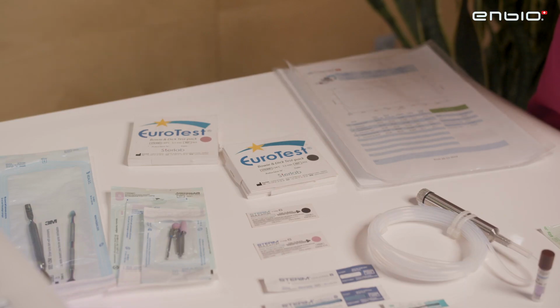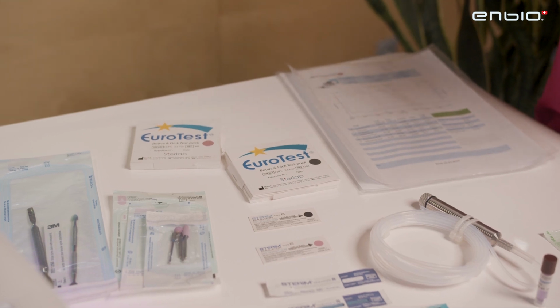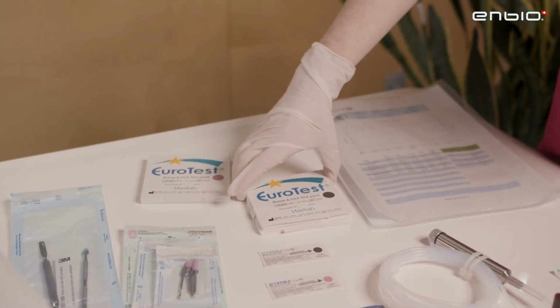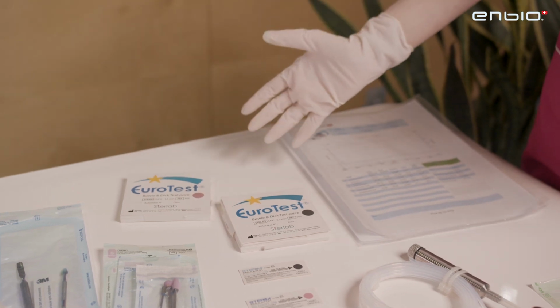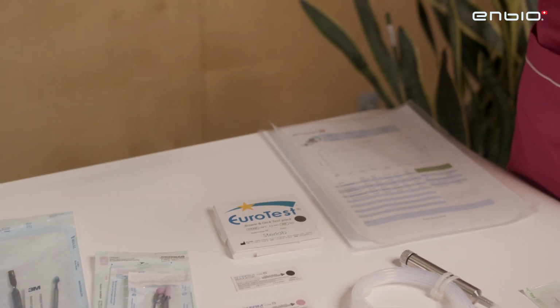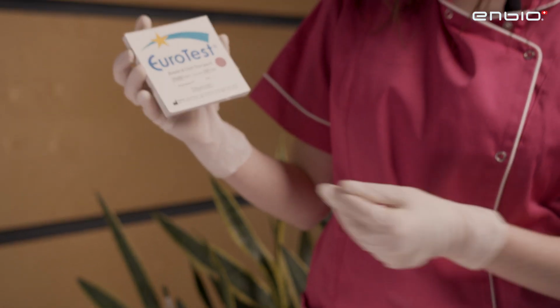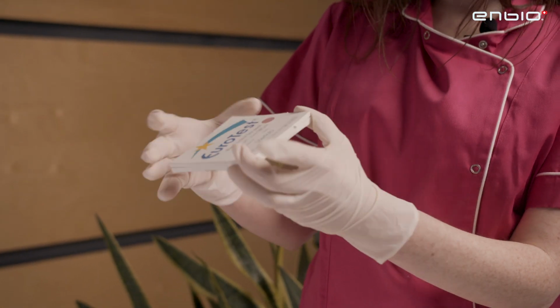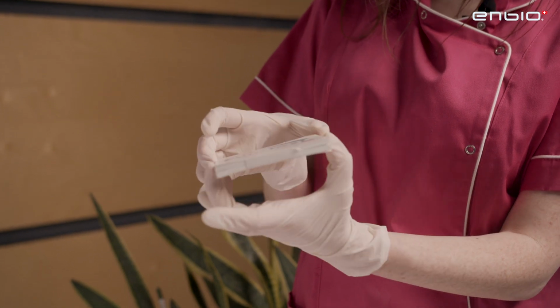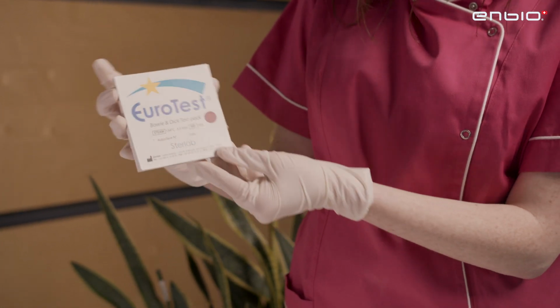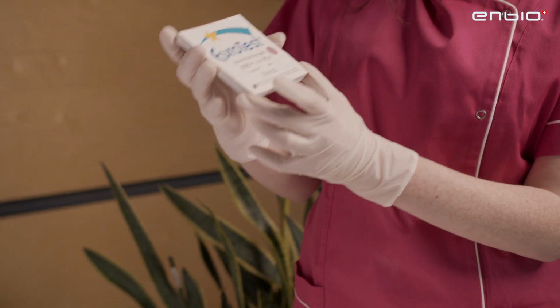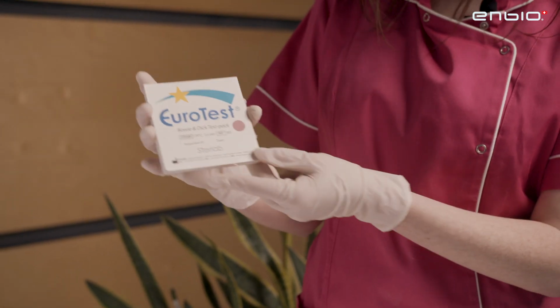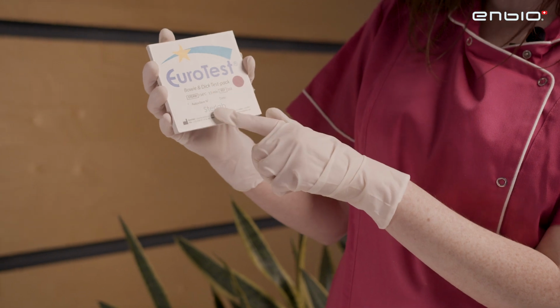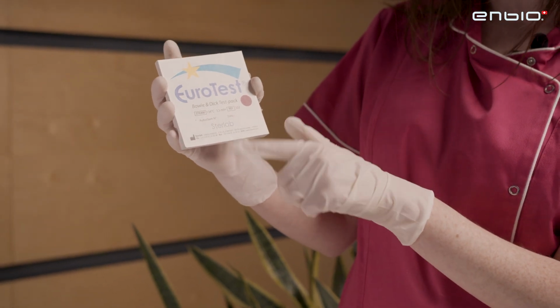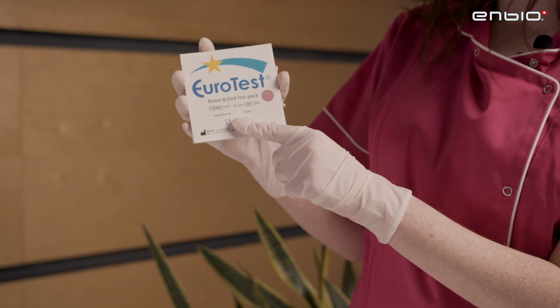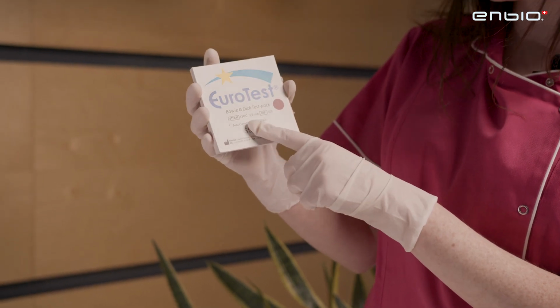Another test that we can perform is the Bowie and Dick test, which analyzes the penetration of the steam during the sterilization process. And this is an example of a Bowie and Dick test. So we can see that it has this format of a closed notebook, if you want. And we have to introduce this test in an autoclave. And for instance, here on the test, we can see that we have to choose a program that sterilizes at a temperature of 134 Celsius degrees.